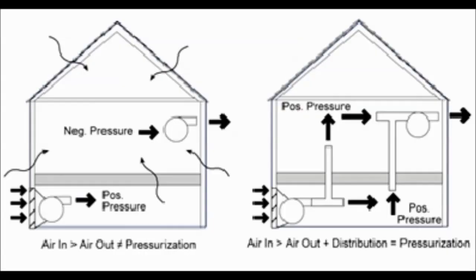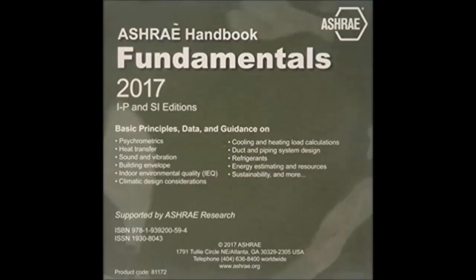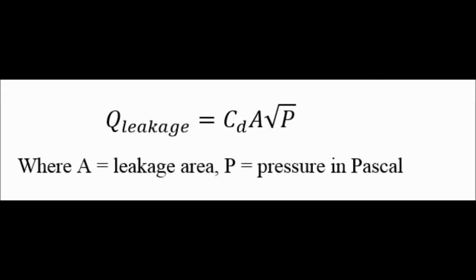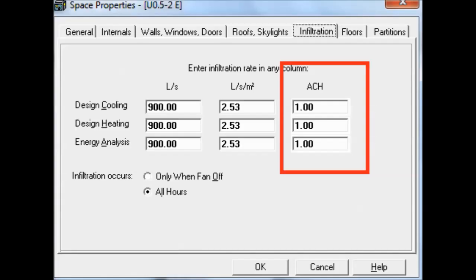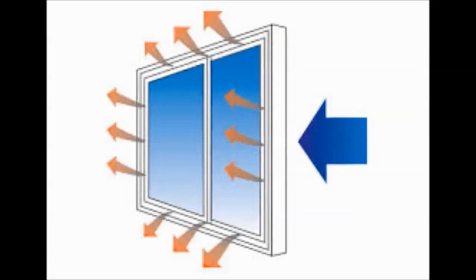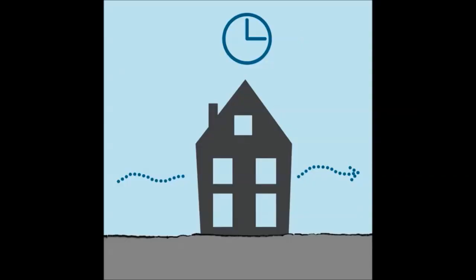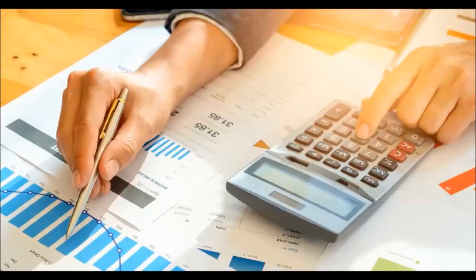ASHRAE Handbook Fundamentals 2001 provides a method of calculation of infiltration, called the crack method, which is given by: infiltration rate in cubic meters per second equals a constant multiplied by the crack area multiplied by the square root of the pressure in pascals. The building initial load calculation is based on an infiltration rate of 1 air change per hour. This means that the air inside the building is going to be fully changed each hour. This value of infiltration is usually assumed for commercial buildings. However, lowering this value is possible but limited to the proper and precise calculation of infiltration.